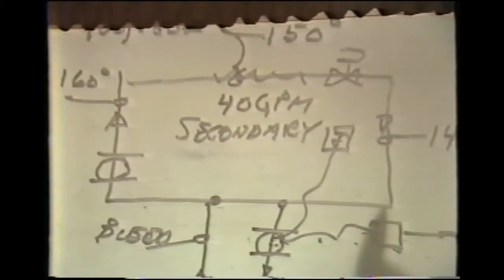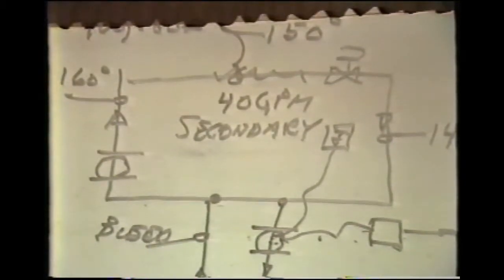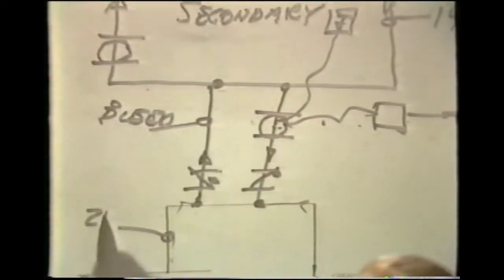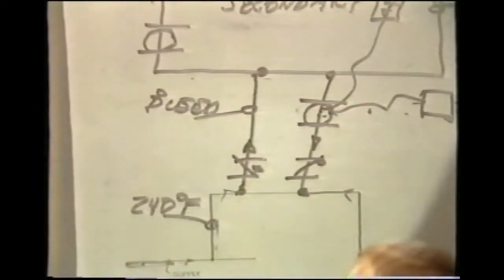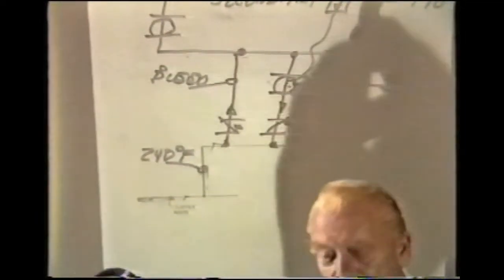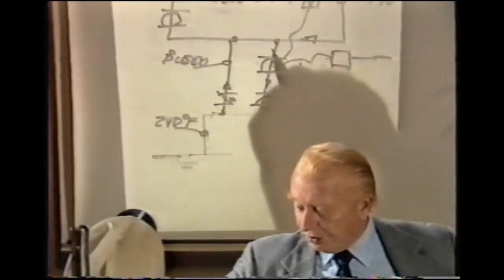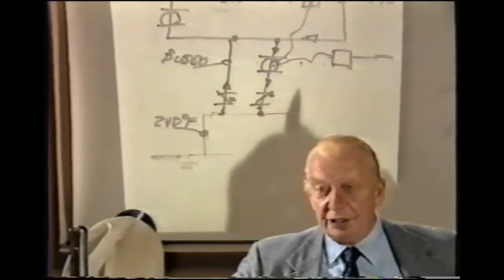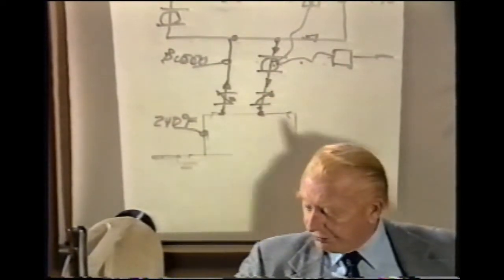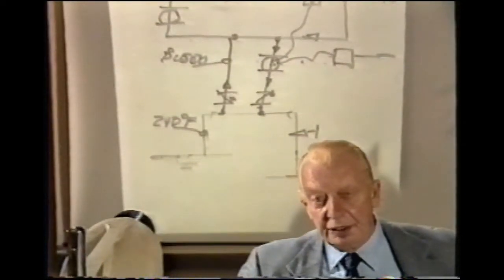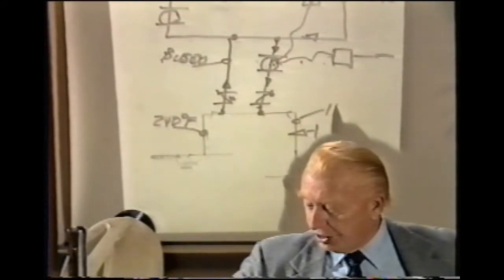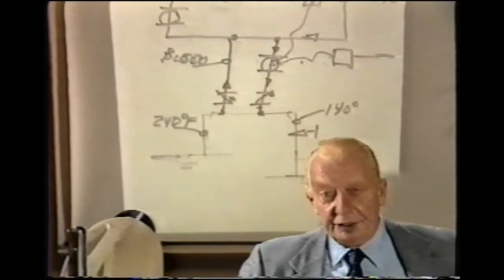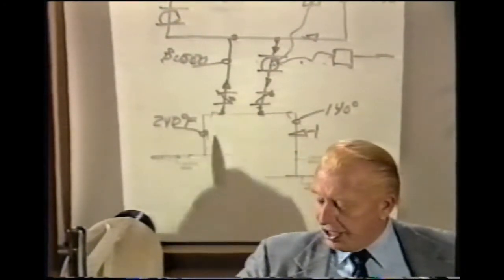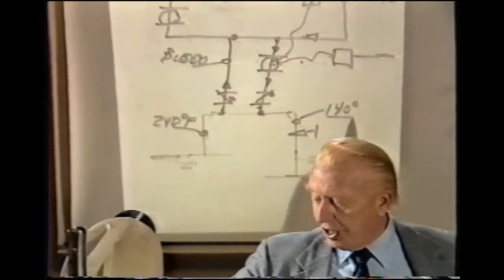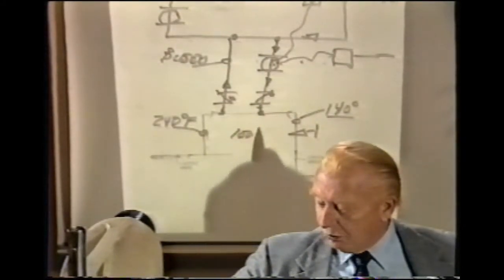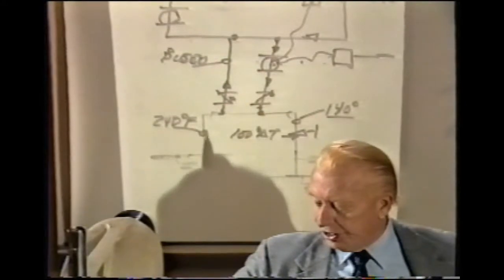Now let's contrast that with the flow rate need in the primary distribution circuit. In the primary distribution circuit, we're going to provide water at a temperature of 240 degrees Fahrenheit. We have 140 degree water returning from the secondary circuit. And that 140 degree water will proceed through the bleed line when the pump is on, and will establish, if we have the secondary circuit crossover bridge in proper flow balance, that we are returning 140 degree water to the basic distribution system. Now, if we provide 240 degree supply and 140 degree return, we have a 100 degree temperature drop across the distribution main.